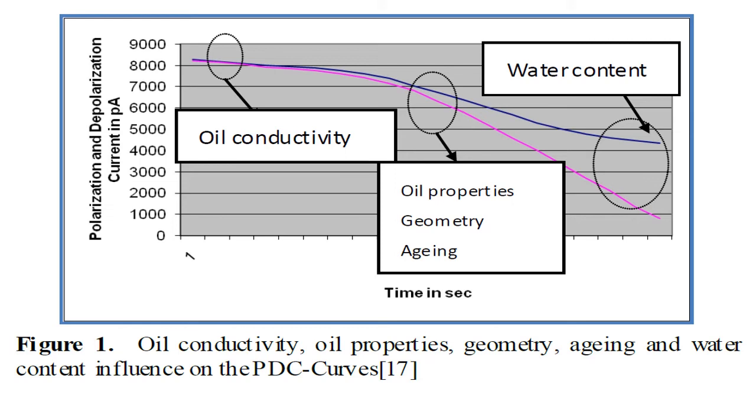Based on the graph, we can check the conductivity of the isolation by checking the front waveforms of the PDC current on the left side. The conductivity affects the polarization currents mainly in the very short time, less than 100 seconds. So the higher conductivity, the higher current value.